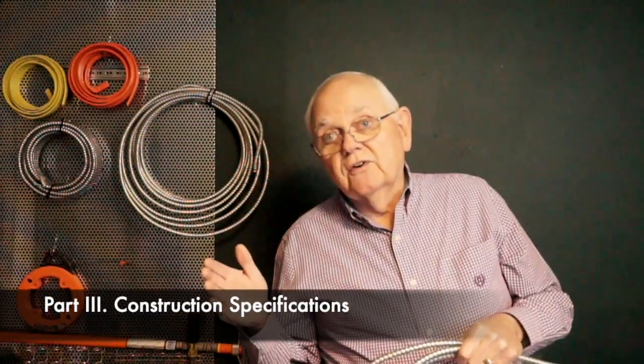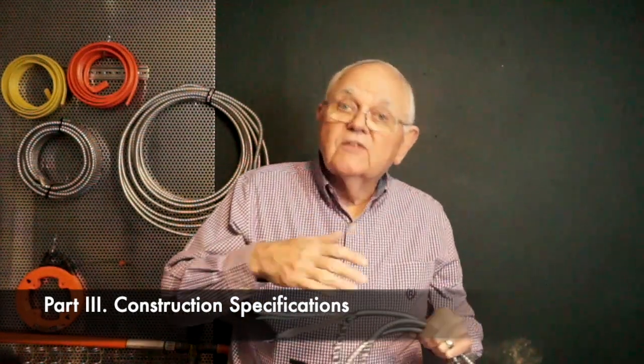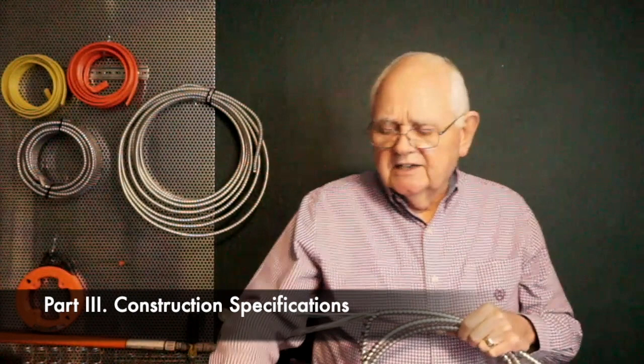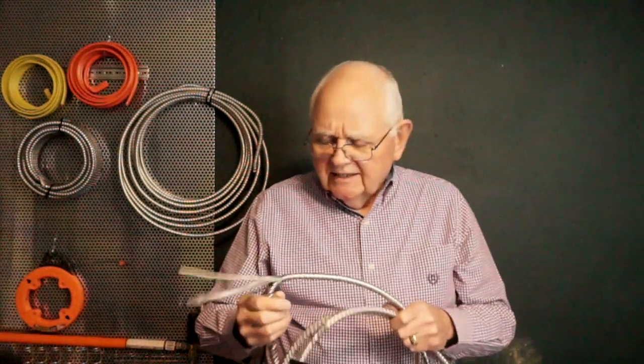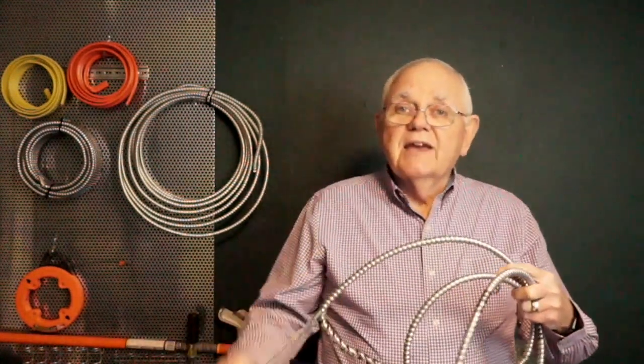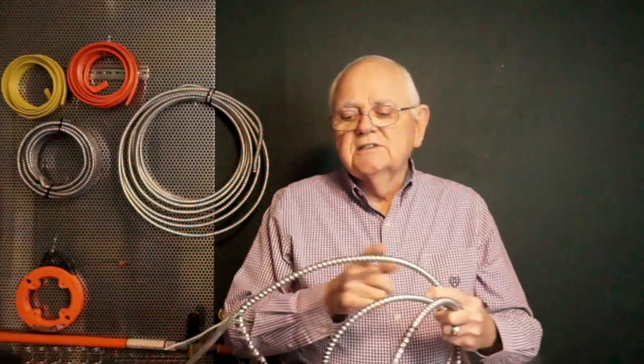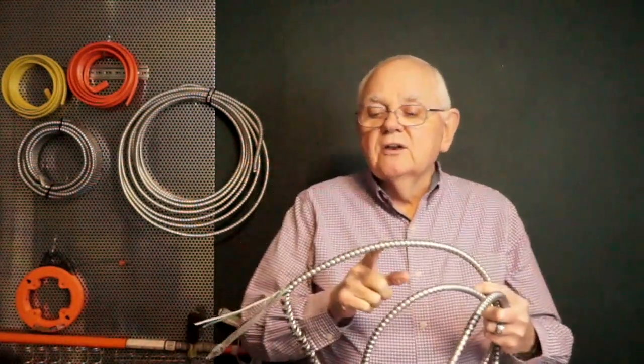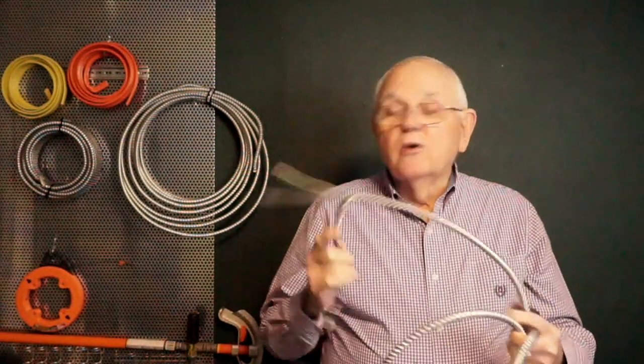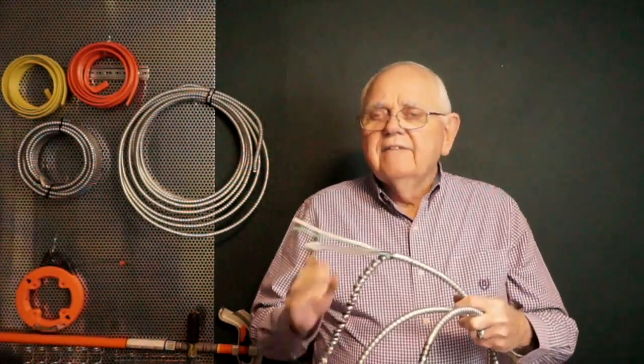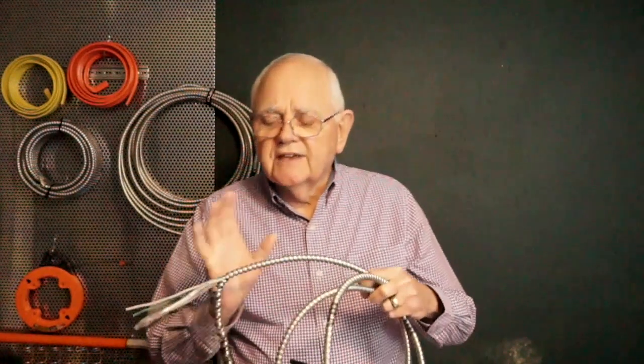So we're actually going to start with the construction specifications. Part 1 is general information of Article 330. Part 2 is installation requirements. And Part 3 is construction specifications. So we'll start with Part 3, construction specifications. And we're going to cover a lot more information than what is covered in Part 3. Anyway, we'll talk about that as we go. So MC type cable, the sheath itself can be either steel or aluminum, and both have advantages and disadvantages. And then there are 3 types of construction of the cable itself.